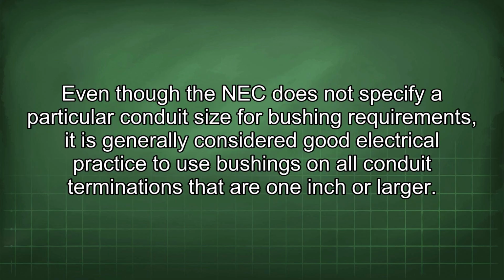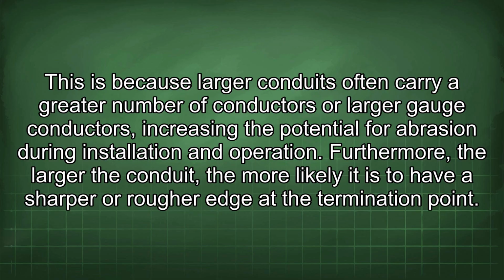Even though the NEC does not specify a particular conduit size for bushing requirements, it is generally considered good electrical practice to use bushings on all conduit terminations that are 1 inch or larger. This is because larger conduits often carry a greater number of conductors or larger gauge conductors, increasing the potential for abrasion during installation and operation.